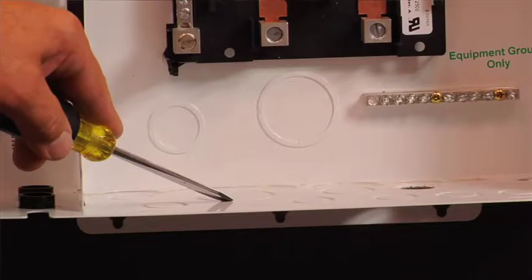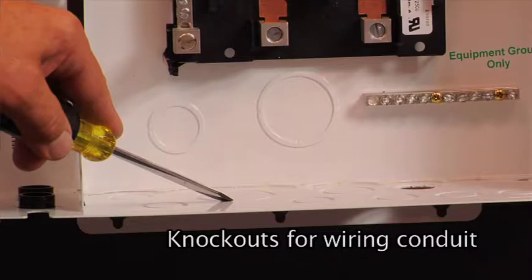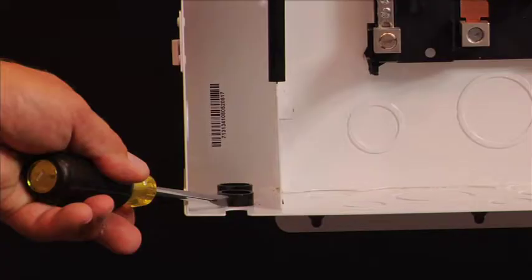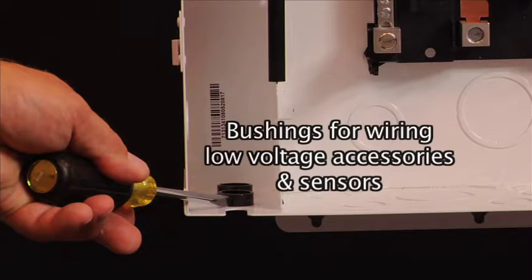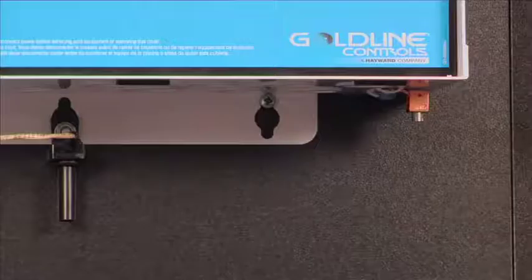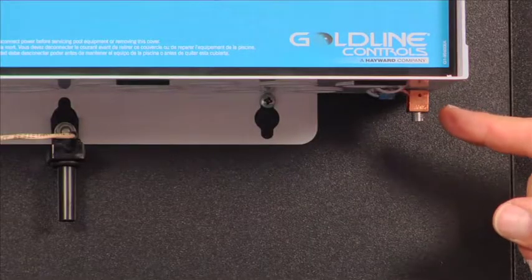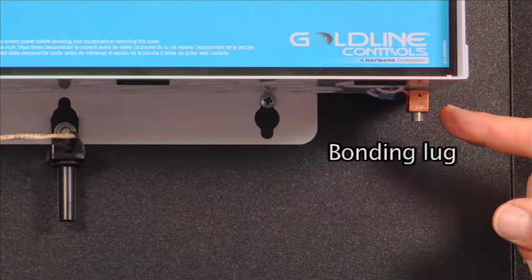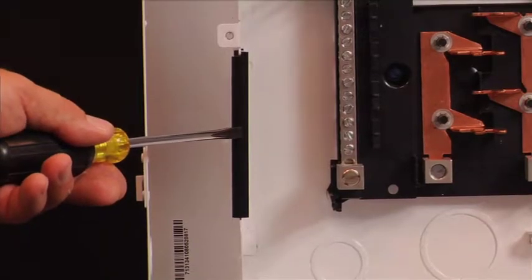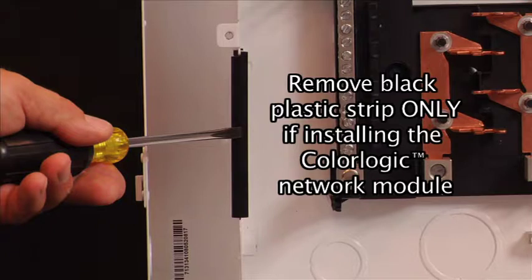On the bottom of the control box are the knockouts to connect the wiring conduit. To the left of the knockouts, in the low voltage compartment, are 2 black bushings. Low voltage accessory wiring and sensor wiring are fed through these bushings. On the outside bottom right corner of the control box is the bonding lug. Use this lug to bond the control box to the other equipment mounted on the pool pad. To the left of the subpanel is a black plastic insert. The insert should only be removed if the Color Logic network module is to be installed.